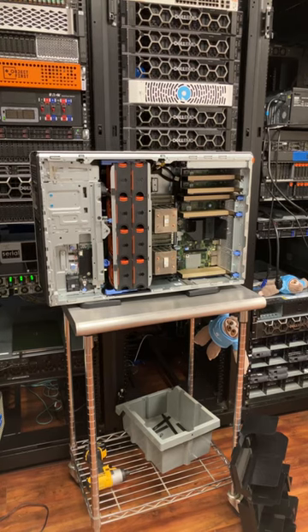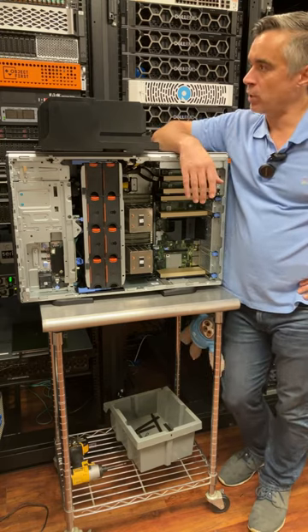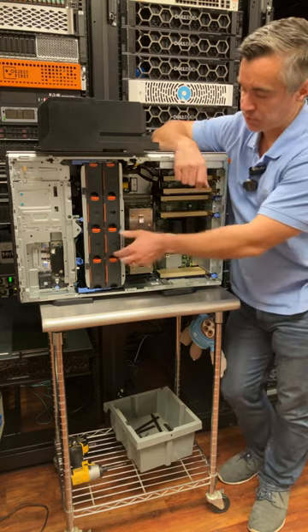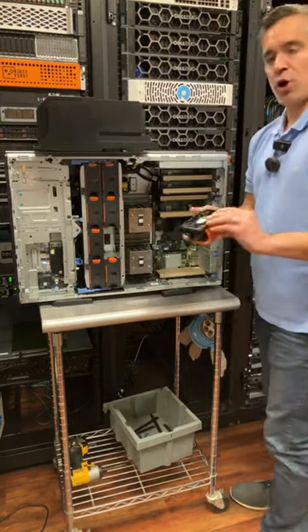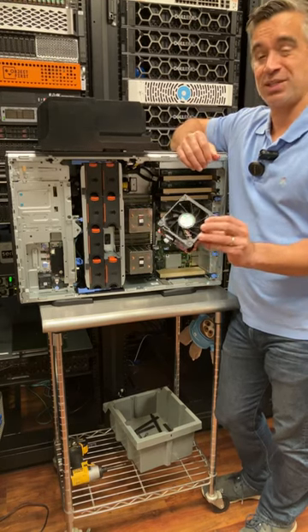So it's pretty impressive, and it's why we don't do much directly with things like acoustics, because for us to create that lab would be such an expensive and heavy lift. And when we run servers in here, of course, we don't hear them. The ones we hear the most, though, are the 1U guys that have the small, super high RPM fans, which are actually substantially louder. Even though these guys are huge, acoustically they put out much less volume than the 1U fans. They don't have to spin as fast to move as much air.